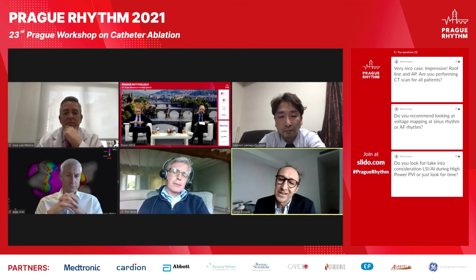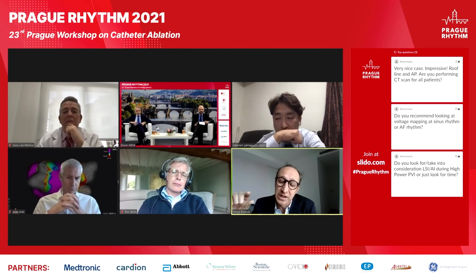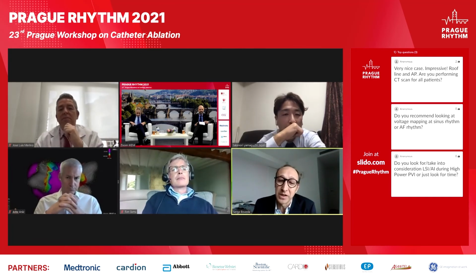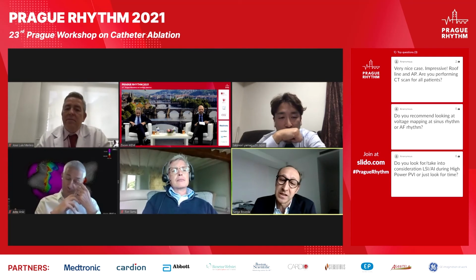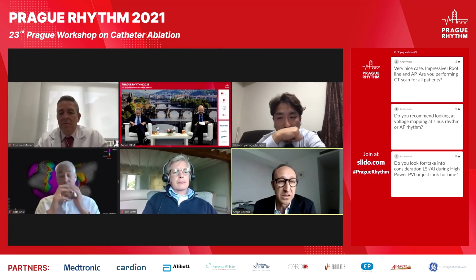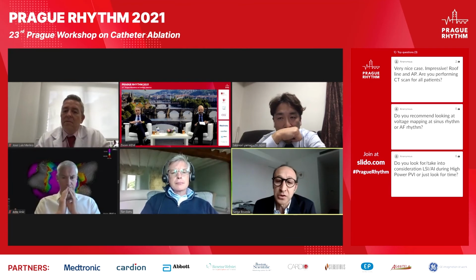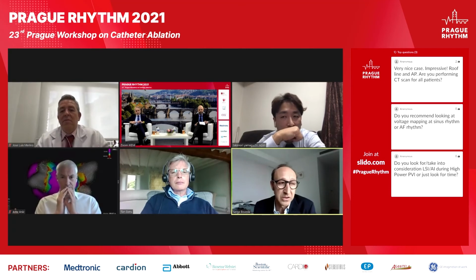So we have a kind of margin between 16 and 12 degrees. So we stop at 16 because you will see that when you are stopping cryo, the temperature is still decreasing a little bit during a few seconds. It's a remnant. It's not an on-off, you know. It's not because you are stopping cryo that it will stop freezing. In fact, the temperature is still decreasing a few seconds, usually about 10 to 20 seconds after stopping. So we decide to stop at 16 degrees.